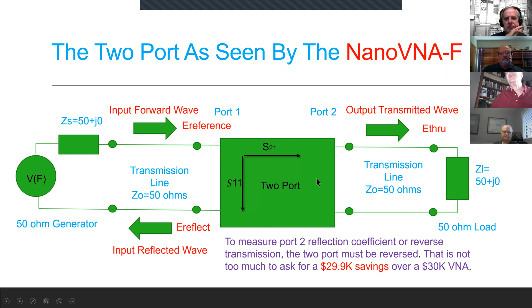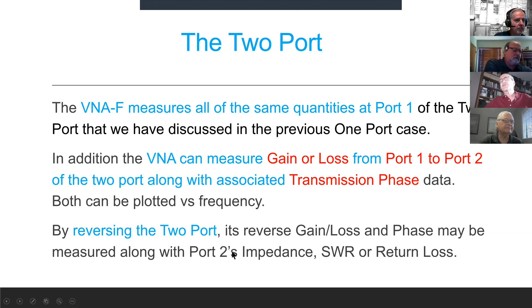The VNA-F measures all the same quantities at port 1 of the 2-port that we've already discussed in the previous 1-port case. In addition, the VNA can measure gain or loss from port 1 to port 2 of the 2-port, along with the transmission phase along the path from port 1 to port 2. Both can be plotted against frequency. And again, by reversing the 2-port, its reverse gain or loss and phase may be measured, along with port 2's input impedance, SWR, or return loss.